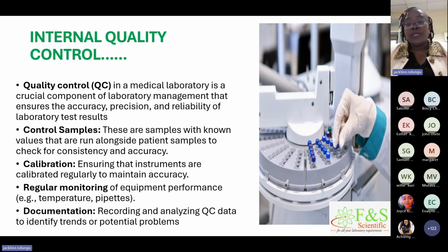So what you do, you get the previous sample from the patient, but something that you need to ensure is that before this specimen was analyzed, the QC was existent. So you analyzed it when the QC was there. Analyze the sample and then check the comparability. What we use and what we recommend is use total allowable error. All this you can get on the website under Westgard rules. You can also use Data Innovations. So compare the two QCs.